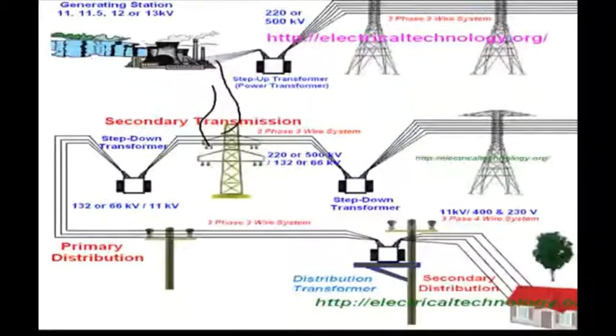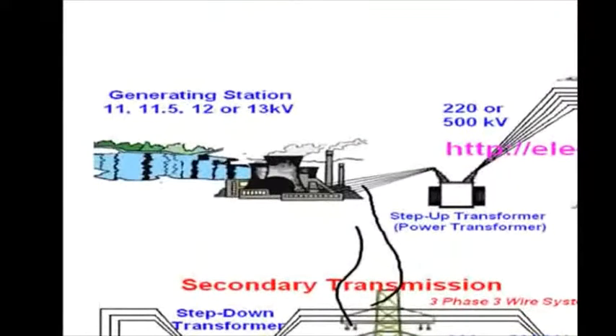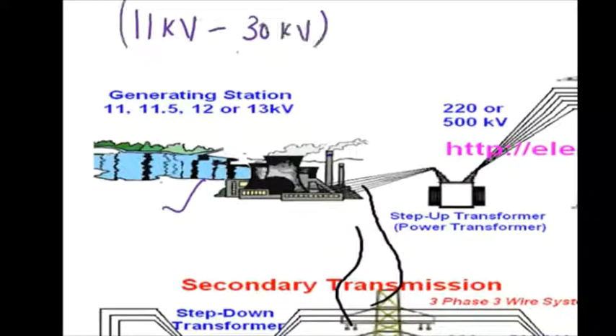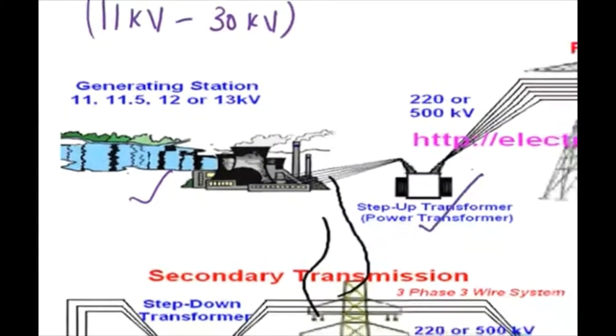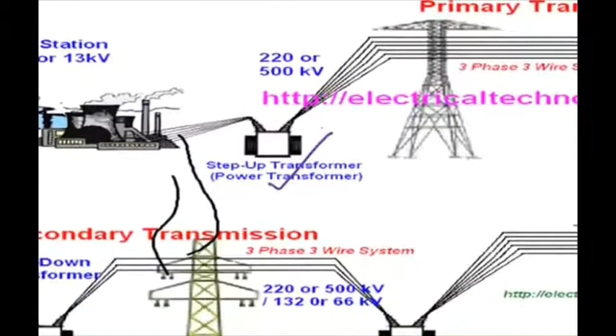Now, if you vaguely understand how the power system works, electricity or electrical energy is generated at generating stations. Usually the generation voltage will be from 11 kV to 13 kV. Nowadays we are generating electricity at voltages from 11 kV to 30 kV. Next, there will be a step up transformer which steps up the voltage from lower voltage to higher voltage, usually in the range of 200 to 500 kV. And then this is a primary transmission.